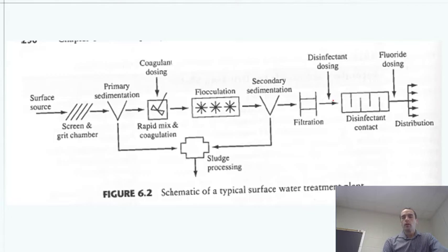And so here, if we're doing a chemical disinfectant, typically what we'll do is we will dose it, and then it will go winding through our disinfectant contactor. You see this is essentially a plug flow reactor. That's by design because if we can let that, let's say chlorine, contact the water for some amount of time, it's a really good thing to have it in a plug flow reactor style, because we don't want some to be immediately mixed from the input with the output.